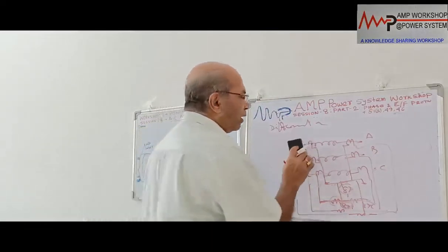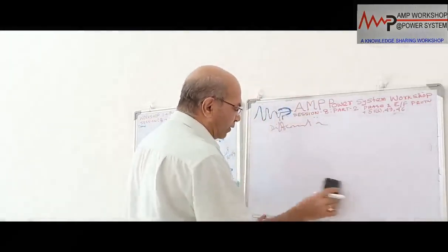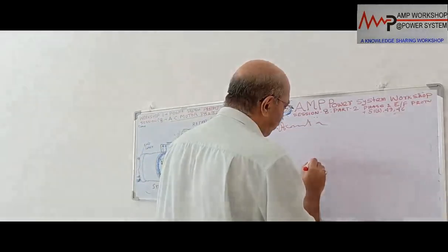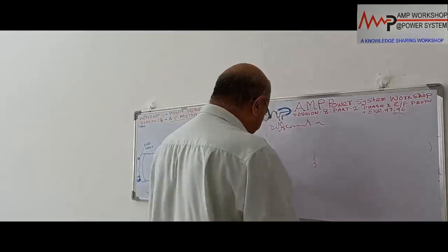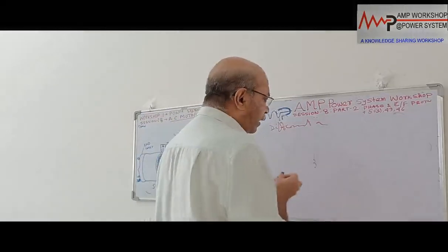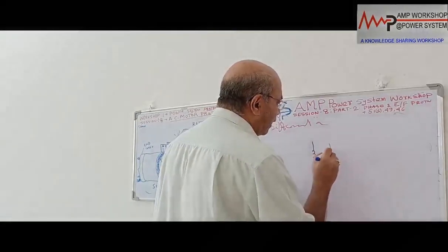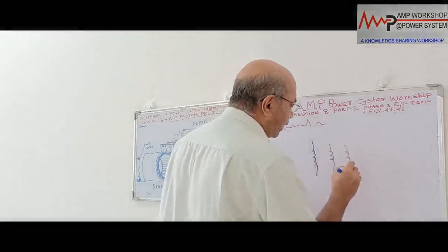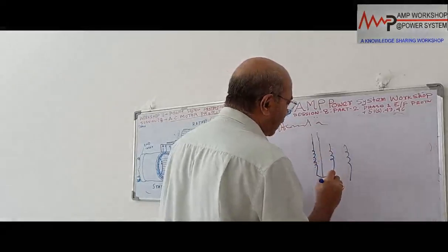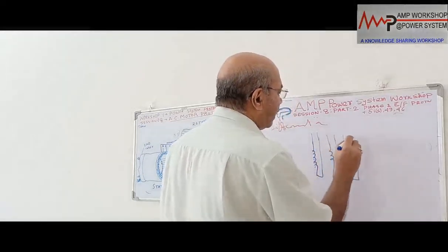In that case, the alternate differential protection we can make is called the self-balanced differential scheme. What do we do in that case? Suppose this is a motor. In the self-balanced differential scheme, we use actually not the differential relay, we use an instantaneous overcurrent relay, but we make the connection in a slightly different way. So these are the 3 windings. In that case, both ends of all these windings will be coming back to the terminal box. This is the requirement to provide a self-balanced differential protection.